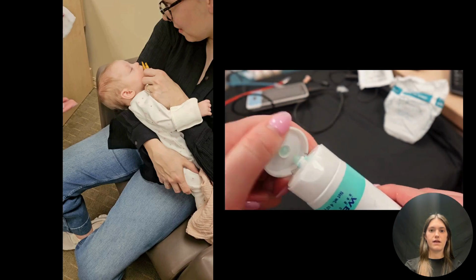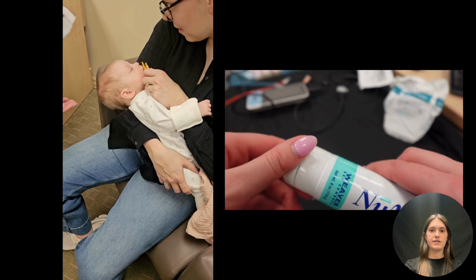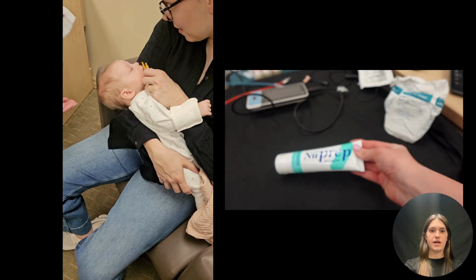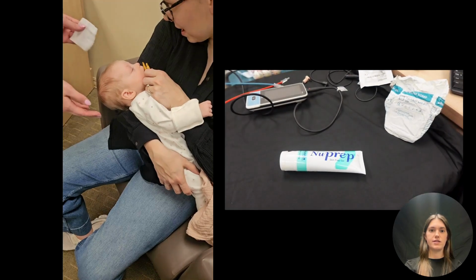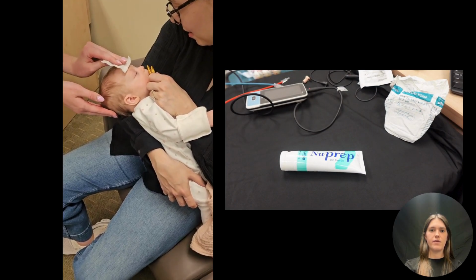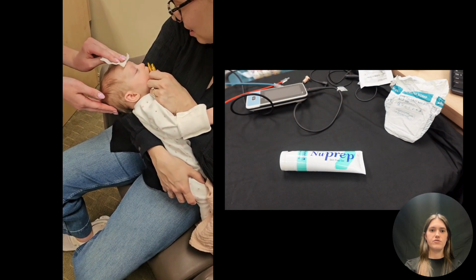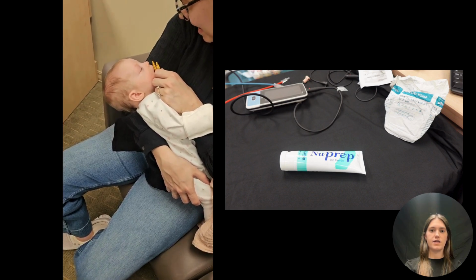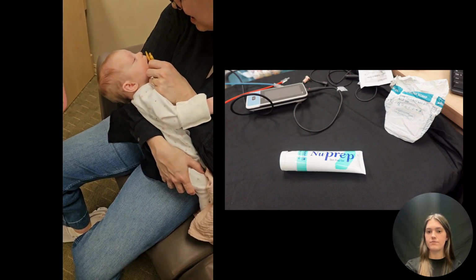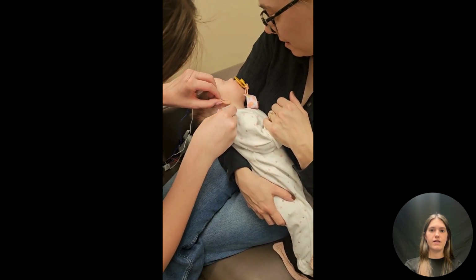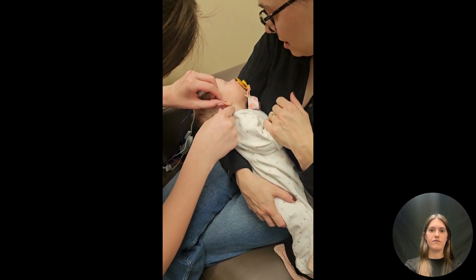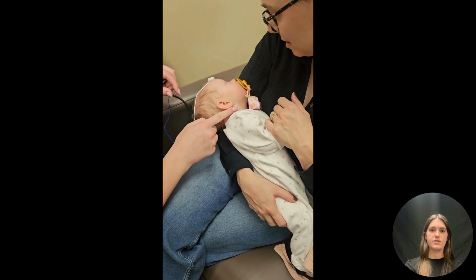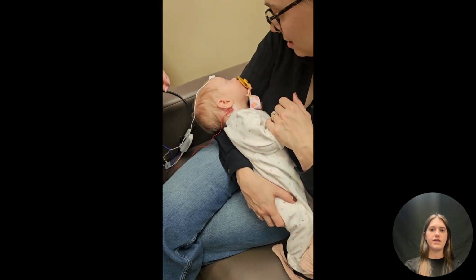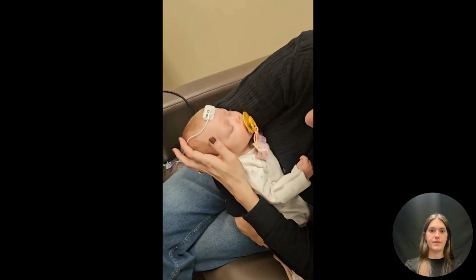If you're having difficulty getting responses, remove the electrodes, clean the skin, and place the electrodes again. Sometimes an alcohol swab is sufficient to clean the baby's skin, but you may find that you have better results if you gently clean the skin with gauze and a product such as NuPrep gel. Occasionally, if an electrode has been removed or has fallen off the skin so many times that it is no longer sticking, you may need to replace it with a new one.